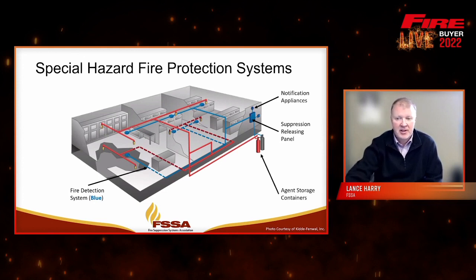We also have the agent storage containers - we'll take a closer look at that in the next slide. But this is a fairly common traditional view of what agent storage containers look like. You've got pressurized cylinders: the red one contains the actual agent, and the gray one contains nitrogen that pushes the agent through the distribution piping network, depicted here in red, and out the nozzles at the end of the pipe network, most commonly brass, but could be stainless steel or other materials. If you look up in the ceiling of a data center, very often you'll see these types of nozzles installed at the ceiling level.